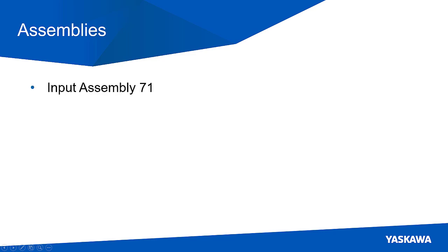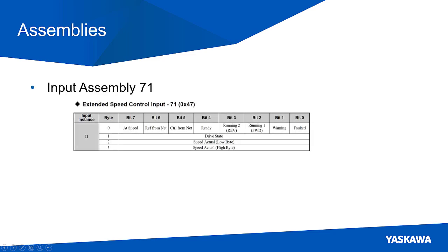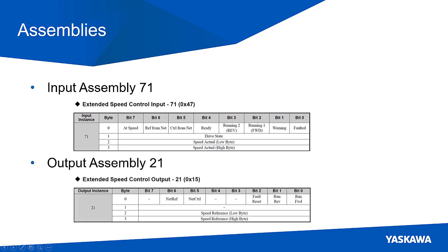Before we start, there are a couple of things that we need to do. First, we need to select our input assembly — the data going to the PLC. Second, we need to select our output assembly — the data going out of the PLC. For this, we'll select input assembly 71 and output assembly 21.